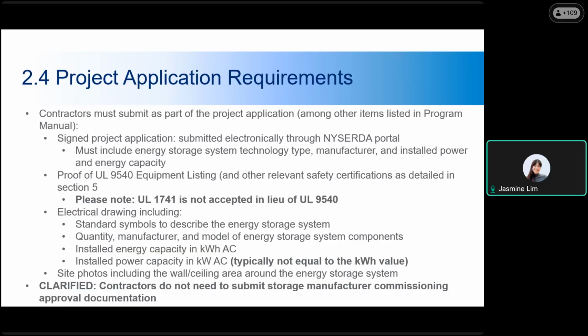On the electrical drawing, we require all the standard symbols: the quantity, manufacturer, model of the energy storage system, the kilowatt hours, and also the kilowatt power capacity, which I want to flag is typically not equal to the kilowatt hour value. This is a common error.